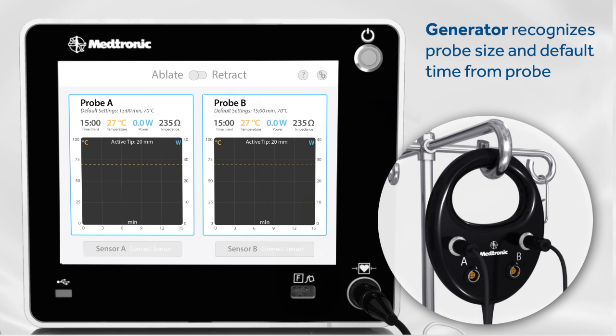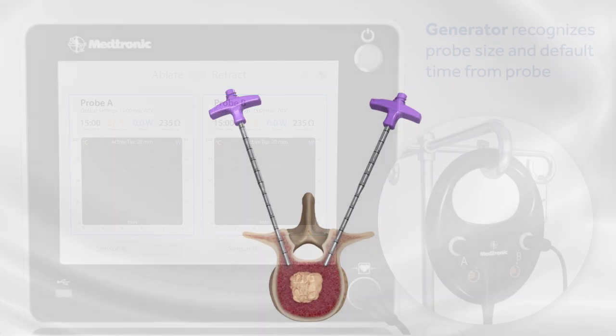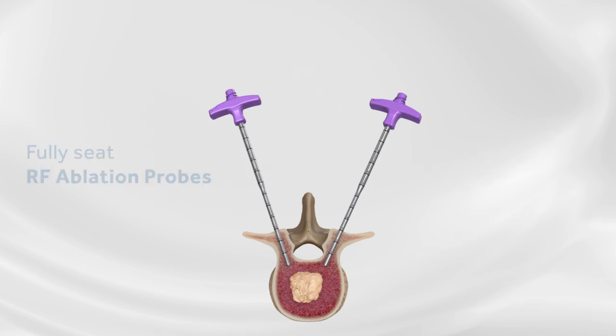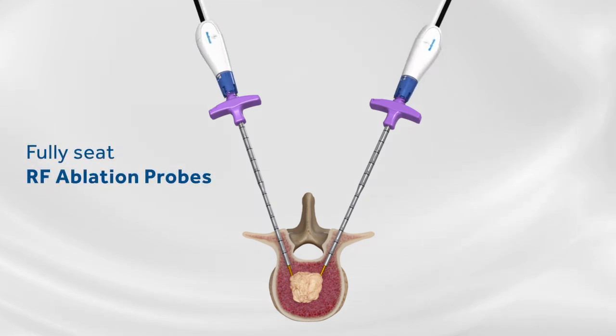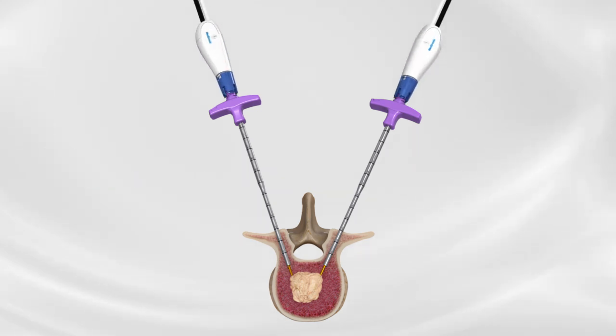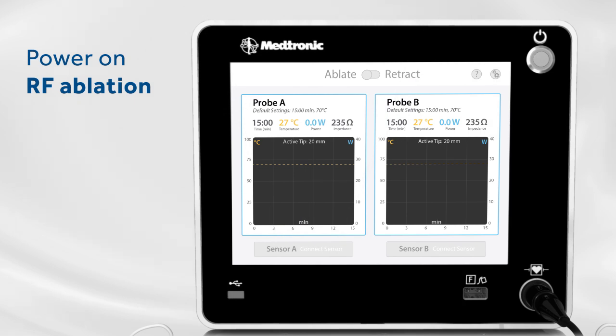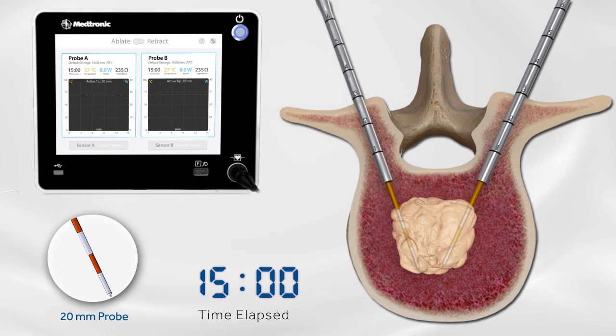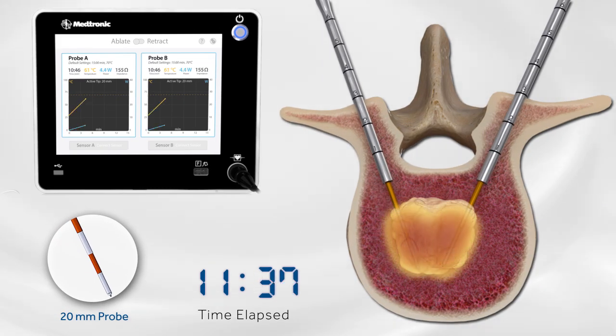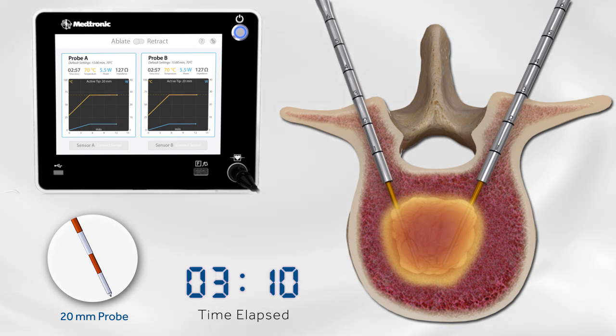Ablation time is preset based on the active tip size of the probe being used. Place the OsteoCool probes through the bone access cannulas, ensuring they are fully seated. Turn on the RF power button. The generator will track temperature and power output over the duration of the procedure. Allow the generator to complete the ablation, monitoring intermittently for any signs of error on the generator screen.